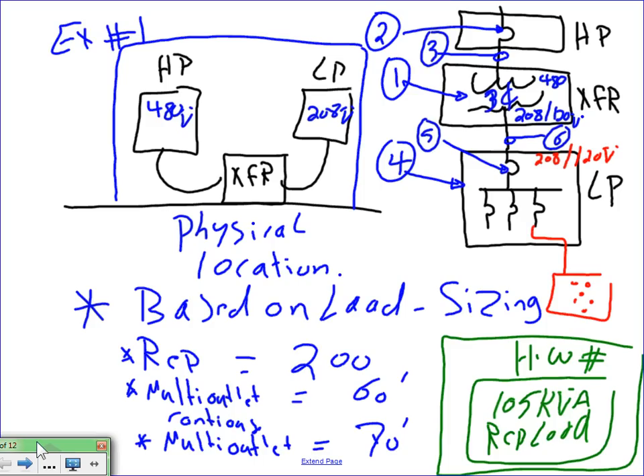In our project, as a matter of fact, the overcurrent protection device for the transformer is going to be in a different room. We don't have this panel. That will be our switchgear, and it will be located in a different location. So that's the physical location. This is the schematic of that system, the one-line diagram.